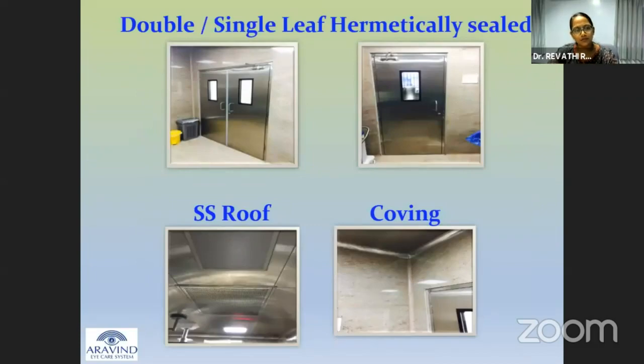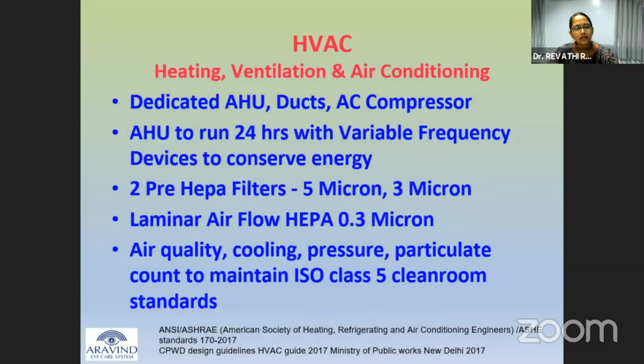The internal physical structures, starting from the doors, could be double or single hermetic stainless steel doors. The roof has to be stainless steel. Coving design is usually preferable because it prevents contamination and dust, and it's easy to clean also. The flooring should have glazed, larger tiles so that minimal or no gaps are present, with minimal joints. Epoxy painting is always preferable for the OT because it gives an additional microbiological cover as well. And always avoid false roofing in the operating theater, especially in the operating theater complex, because it is difficult to clean. Air is an important culprit which has to be kept in mind.